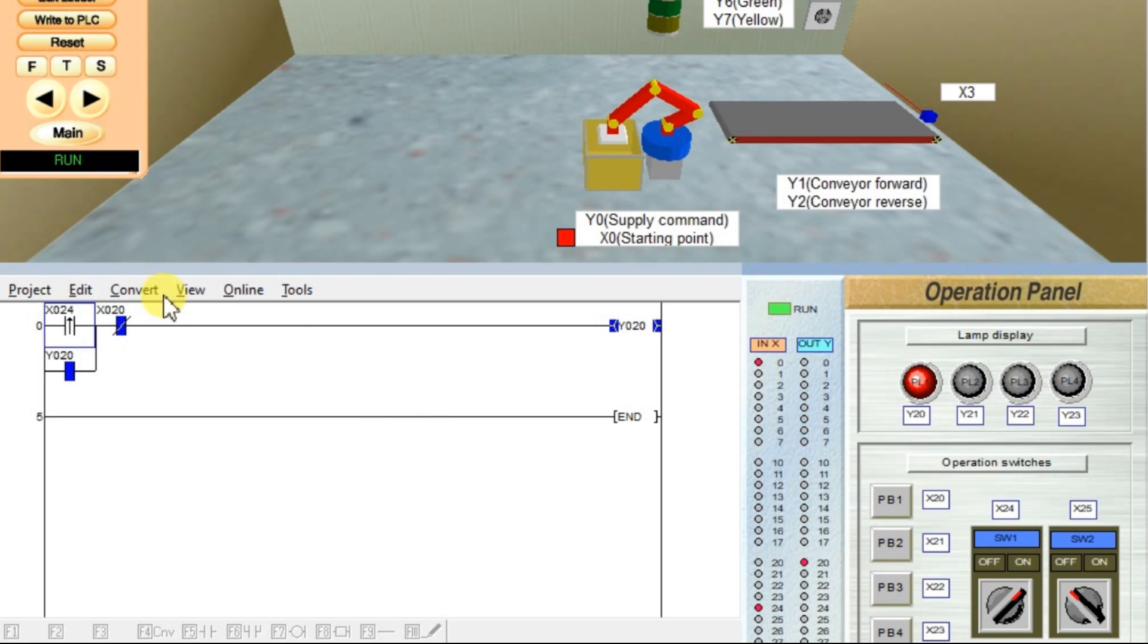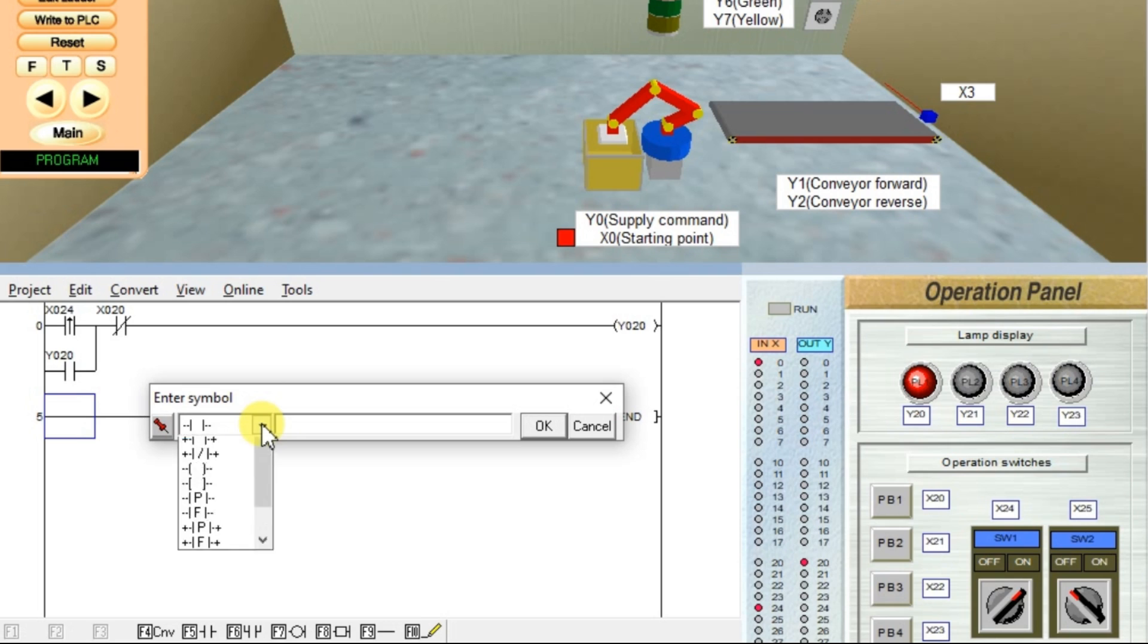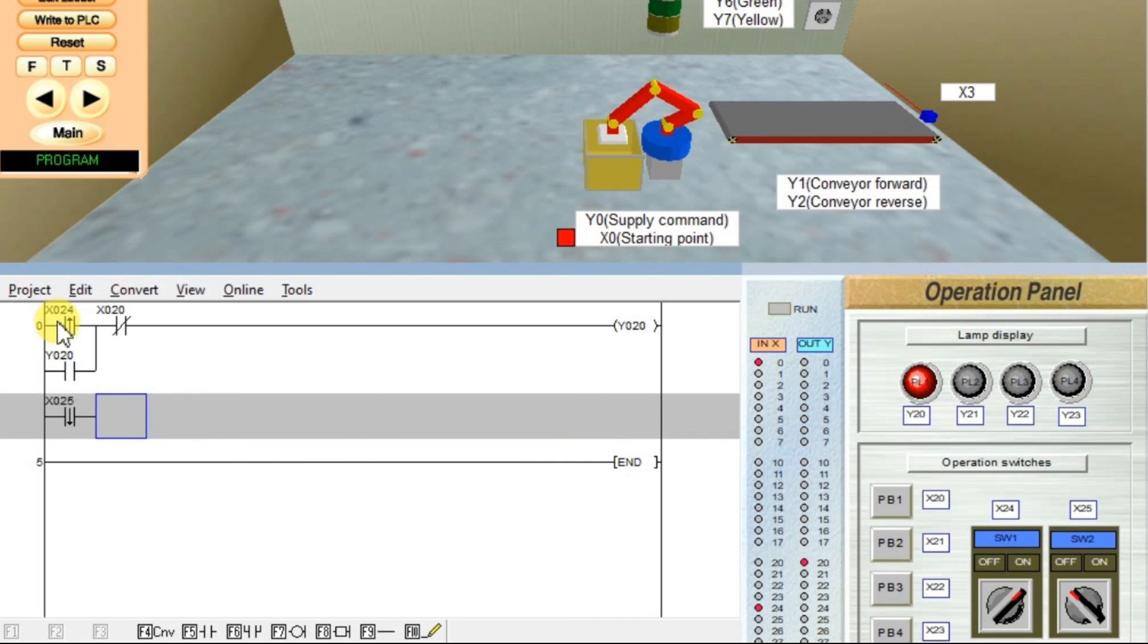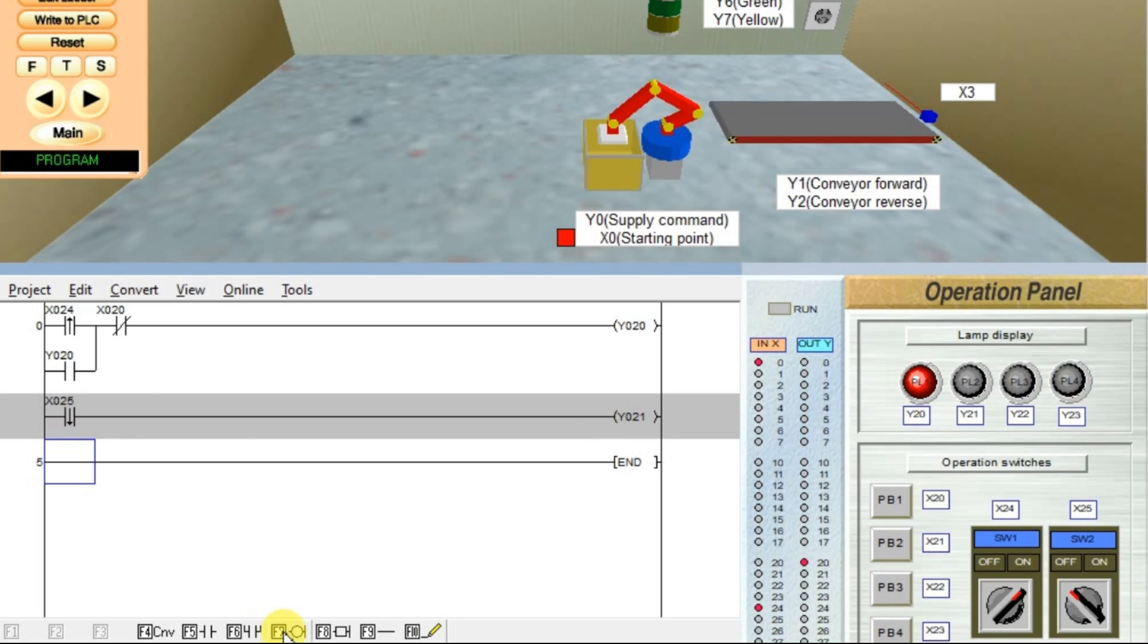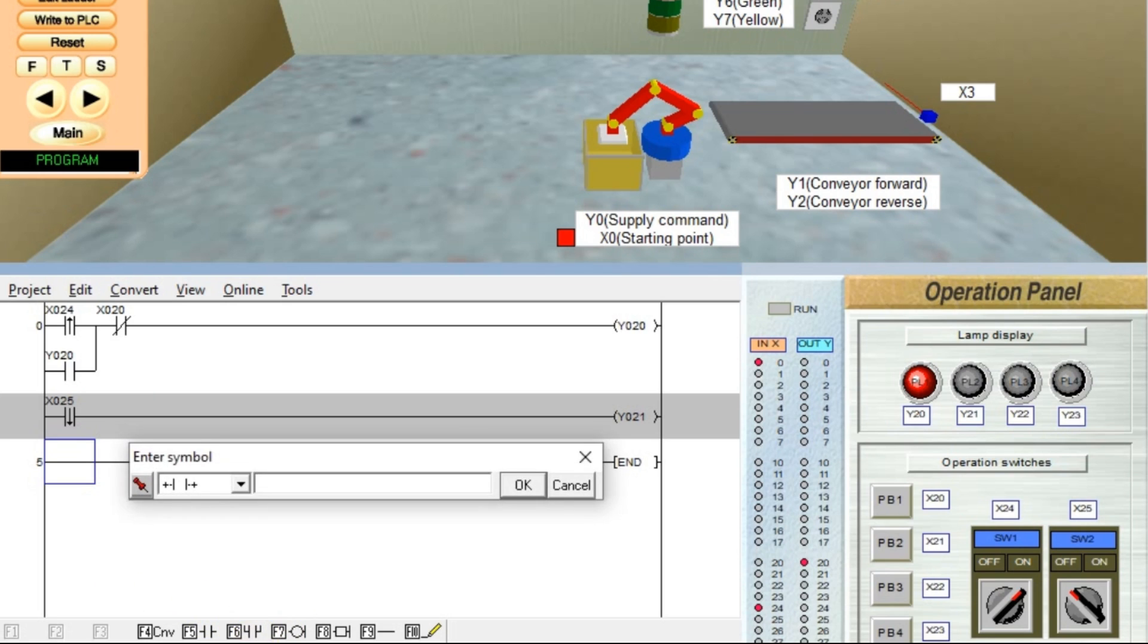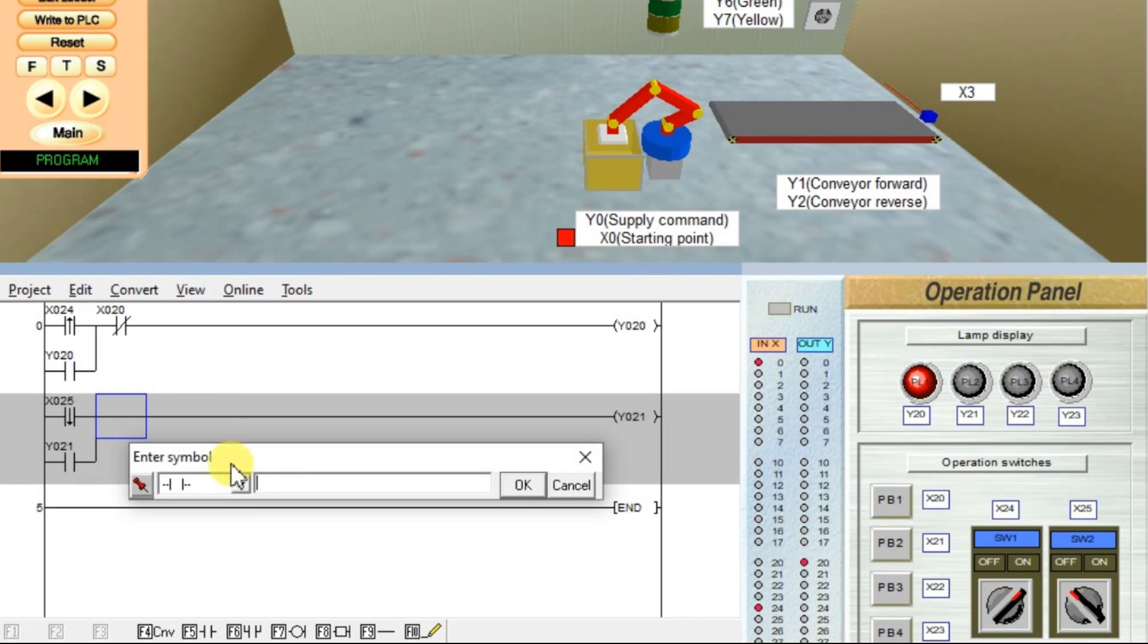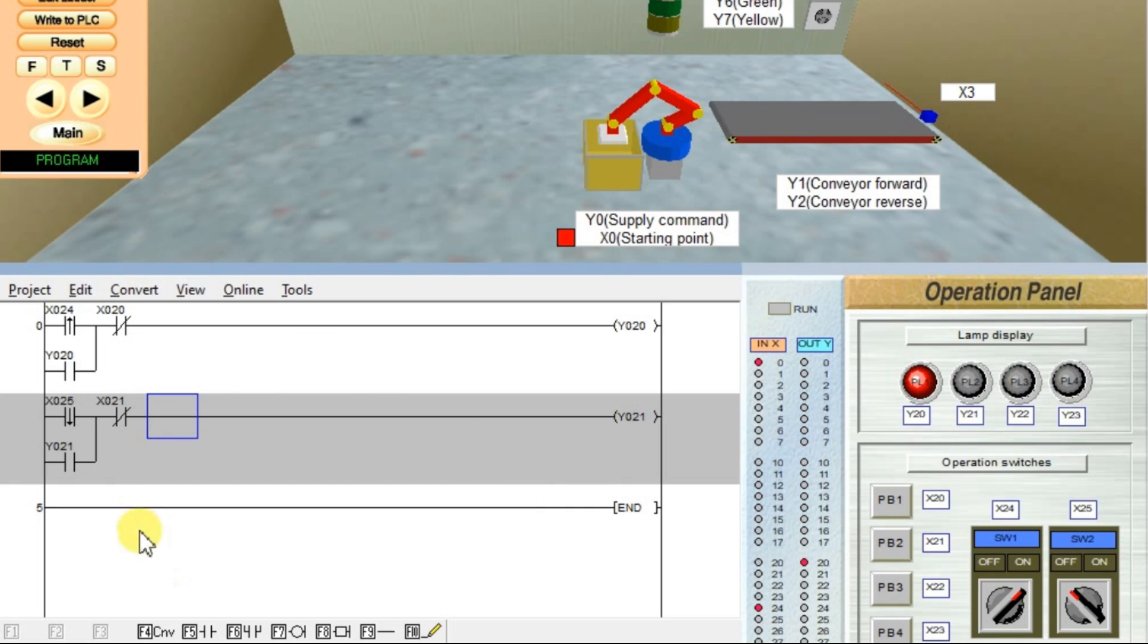Similarly, we will see the falling edge. Click edit ladder. Take one input. Falling edge is with F, represented with F. Enter one input X25, OK. And on output I will take Y21. So I will latch it, Y21. Again, for resetting purpose I will add one more push button. We have to take NC contact. X22 or X21, click OK. Convert it, write to PLC.